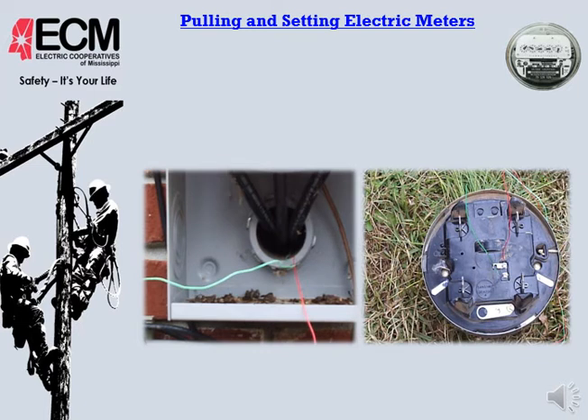On this one here, again, we really need to be paying attention. You'll notice the green and red wire going into the house through the conduit, where the entrance wires go into the house or building. The picture to the right is where they've tied the other end of those wires, where the meter is usually strapped out so it can register - that's tied together there, and you'll see they've got the strap removed. On the inside of the house, the green and red wire was tied to a switch where they could manually open and close it to make the meter register. So again, this was something learned off an internet video.